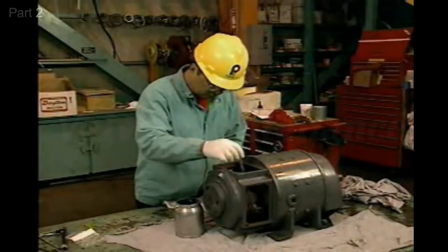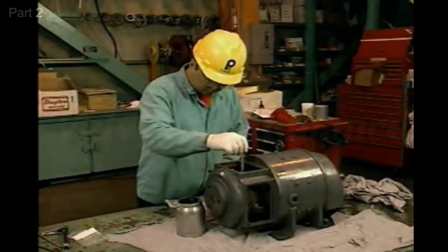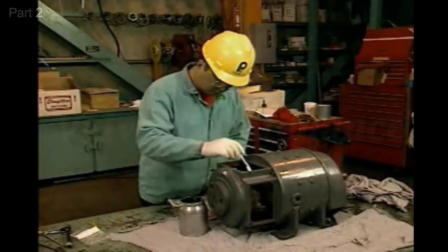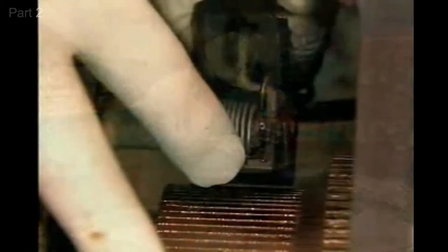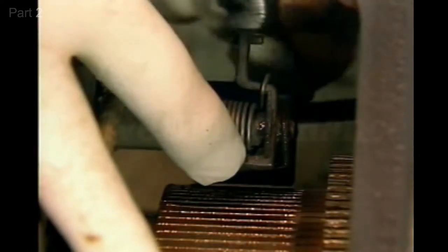During the cleaning step, it's important to pay special attention to the brush holders, the brush tensioning devices, and the commutator. The brushes can be removed from their holders so that the inside of the holders can be cleaned.